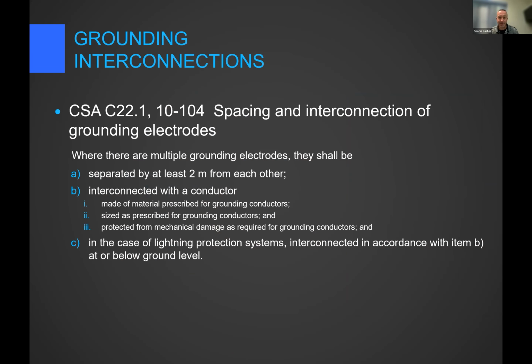Here we go, back to the interconnections. And I do want to clarify this point. You all know this already from your electrical inspecting, but I figured it was worth it to go over the code in detail here. Separated by 2 meters from each other, interconnected with a conductor. This is a deliberate interconnection made of a material prescribed for grounding conductors, sized as prescribed, and protected from mechanical damage. In the case of lightning protection systems, interconnected in accordance with the above, at or below ground level. So we have to make our interconnection with the electrical ground at or below ground level. That could also include an electrical room on the ground floor with a main ground bus. We are allowed to make that connection there. That's fine.